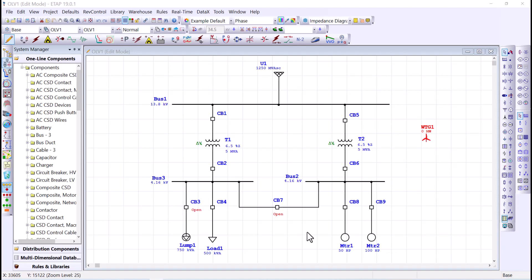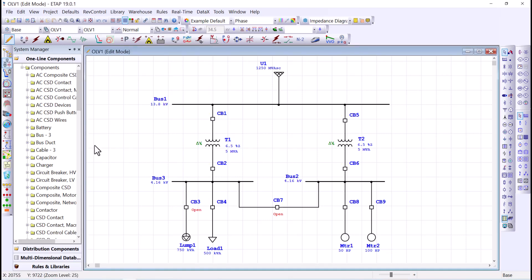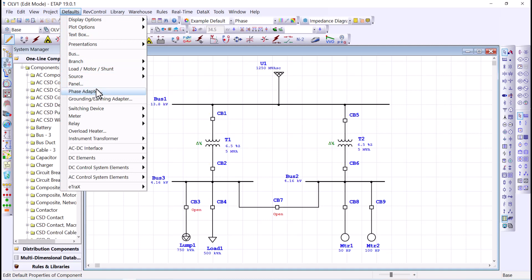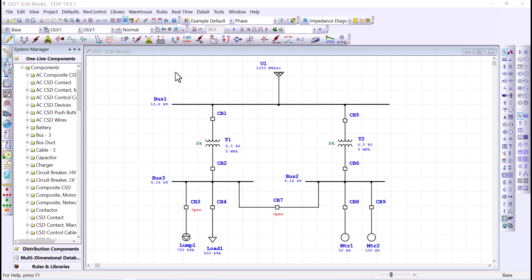The fifth tip is related to component IDs. Every element in ETAP requires a unique ID. When you add new elements, ETAP automatically assigns an ID by appending a number to the default ID. You can find the default IDs by going to Defaults — for example, for induction motors the default ID is MTR. If you need to change the component ID to something that meets your needs, simply change it here, keeping in mind you are limited to 25 characters.